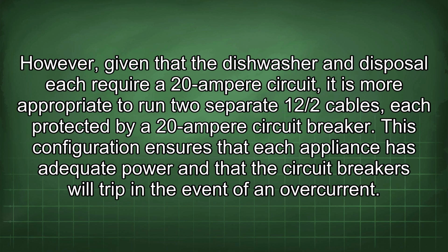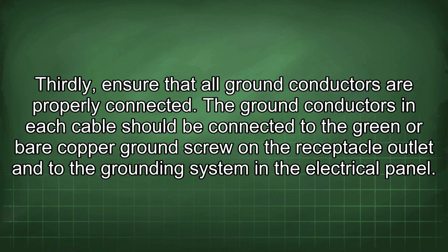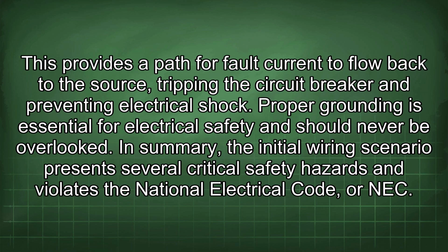an overcurrent. Thirdly, ensure that all ground conductors are properly connected. The ground conductors in each cable should be connected to the green or bare copper ground screw on the receptacle outlet and to the grounding system in the electrical panel. This provides a path for fault current to flow back to the source, tripping the circuit breaker and preventing electrical shock. Proper grounding is essential for electrical safety and should never be overlooked.